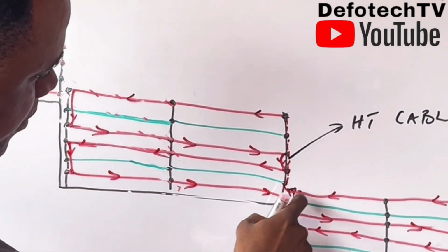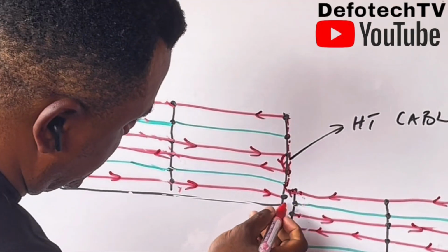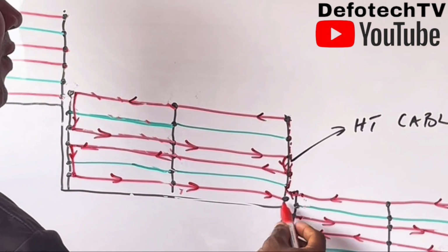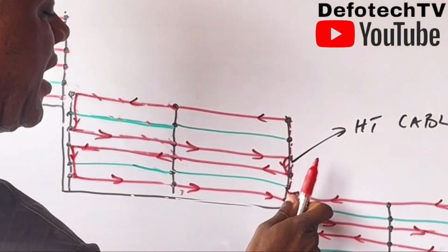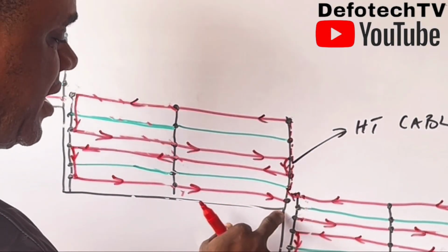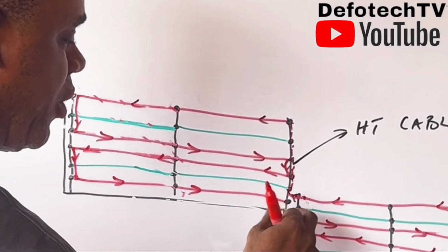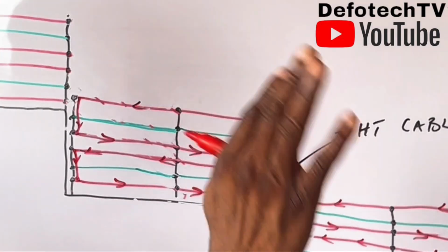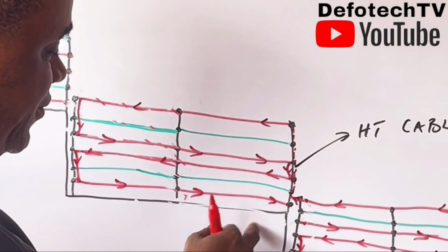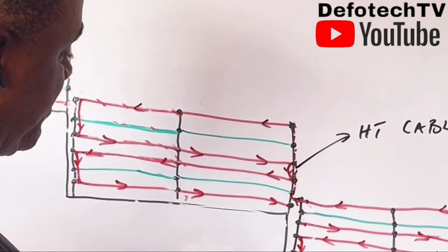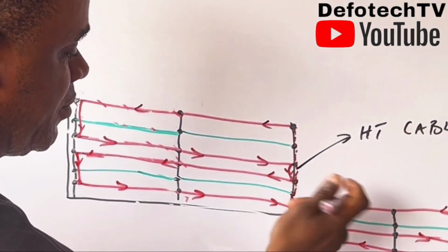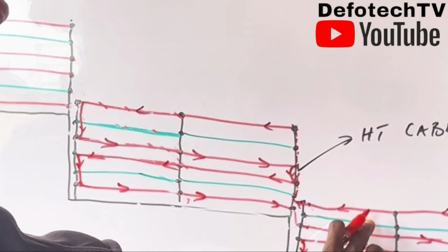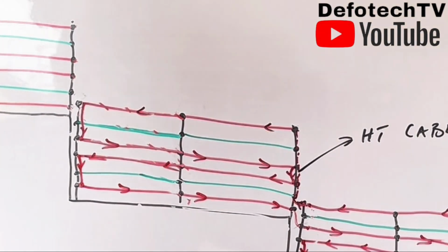Now, you know we've opened this terminal here, so I'll take this one from here with the same HT cable. If it's not going to touch, if there is a way, you can just hit it without any contact with either the fence, the bracket, or anything. If the direct wire with the aluminum wire can link directly, fine. But if it's going to touch anything like maybe the fence, the bracket, those parts, please use the HT cable here also. Link this to this. I've not touched the earth. We'll deal with that, please, in case I forget.